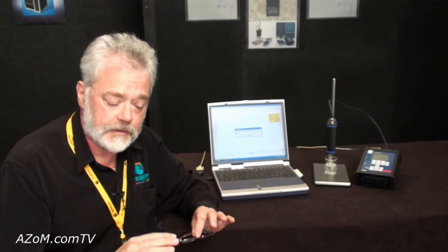What about other coating industries and things like that? Paints are another industry which these things should be used routinely, particularly spray paints, things where there's a high activity in the nozzle area for a spray paint, or for spray painting applications in the automotive industry, where the formulation of the paint's very important to get a clean spray out of the nozzle. So anything which has a susceptibility to surface tension in a high shear environment, a dynamic surface tensiometer is the correct way to measure that particular parameter.